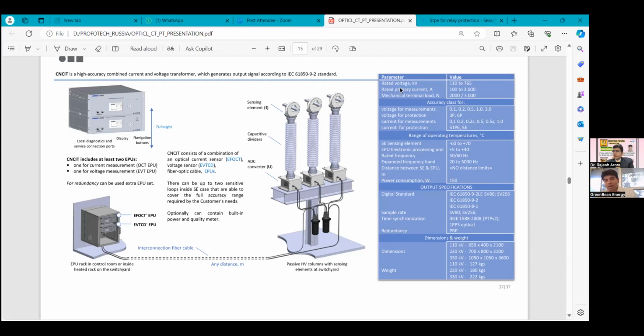So this current voltage transformer can measure from 110 to 765 kV, rated current from 100 to 3000 ampere, and mechanical terminal load 2000 and 3000. Voltage for measurement 0.1, 0.2, 0.5, 1 and 3 accuracy class. Voltage for protection 3P, 6P. Current for measurement 0.1, 0.2, 0.2S, 0.5, 0.5S, 1. Current for protection 5TPE.